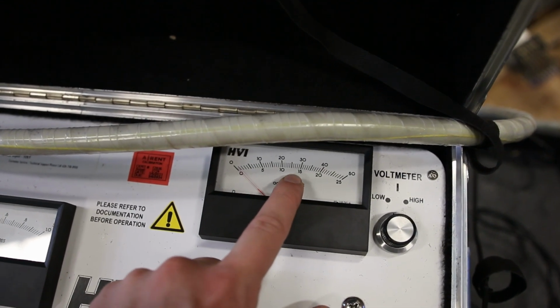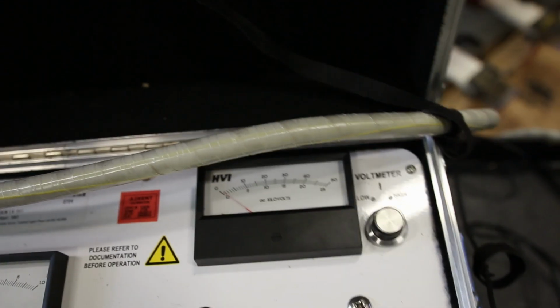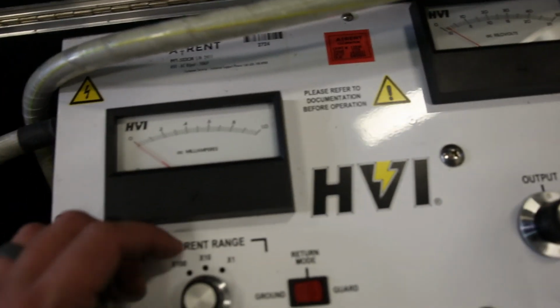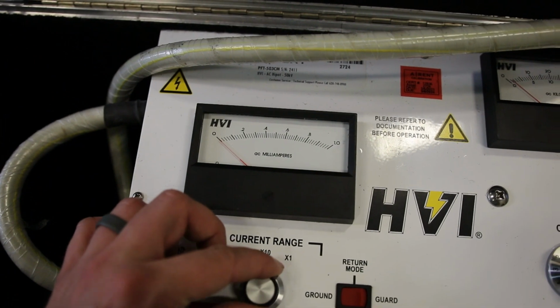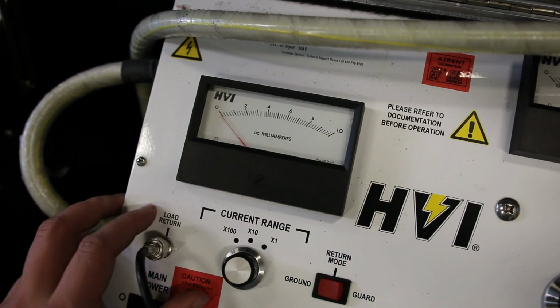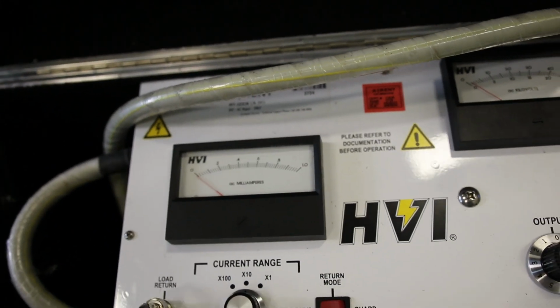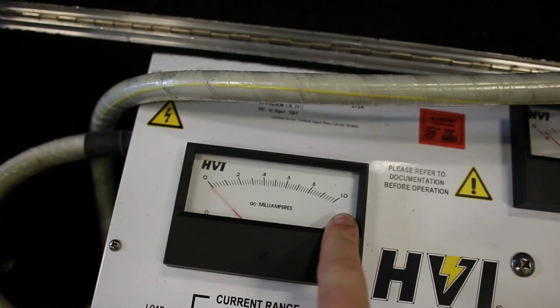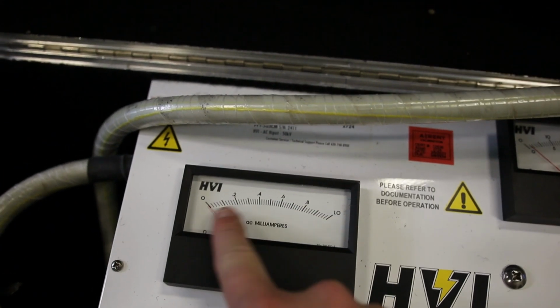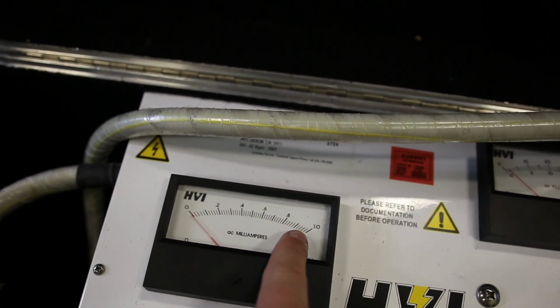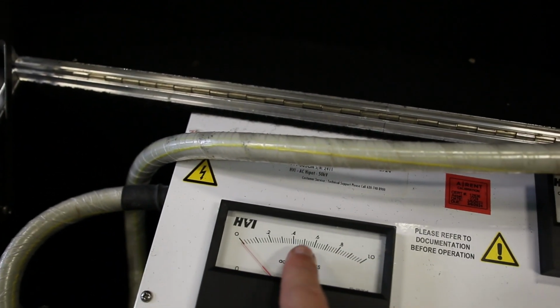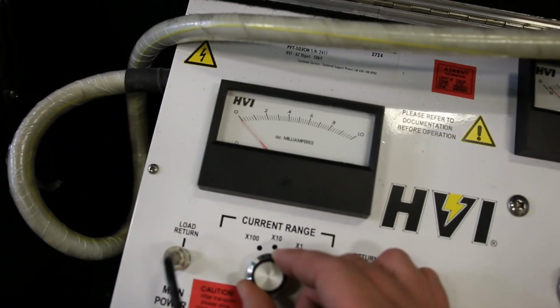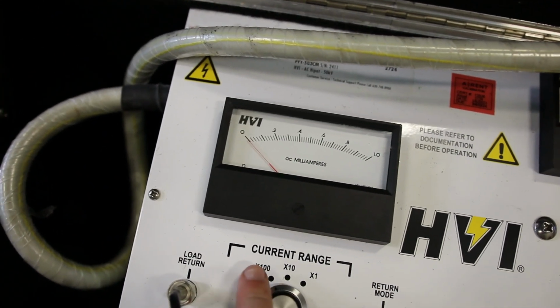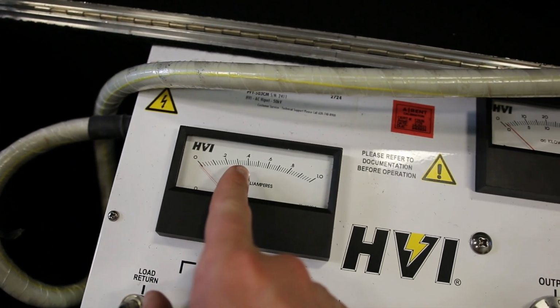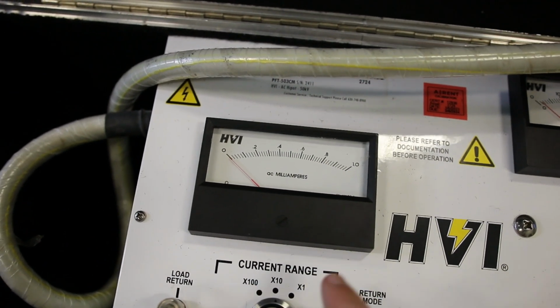And we're going to go to just below the 15 kV AC spot. I've done this a handful of times, so I'm going to assume this selector, I don't know if you can see the arrow on that, it's pretty small, we're going to go to the 10 times range. It's whatever this is times 10. So instead of 0.2, 0.4, 0.6, 0.8, 1, it's 2, 4, 6, 8, 10. If we were in the high range on the 100 times multiplier, it would be 20 milliamps, 40, 60, 80, and 100 milliamps, but we're not. We're on the 10 times range. I think that's where we need to be.